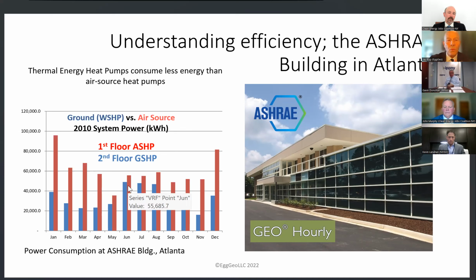Now pay attention to one more thing: this summertime peak for the heat pumps—if you look at the geothermal, the wintertime peak doesn't even hit summertime levels. That means we've solved a wintertime peaking problem with all-electric systems. If we upgrade all our buildings to a thermal energy network, our winter peak could theoretically be at or below our summer peak, leveling out the grid, as you can see here.